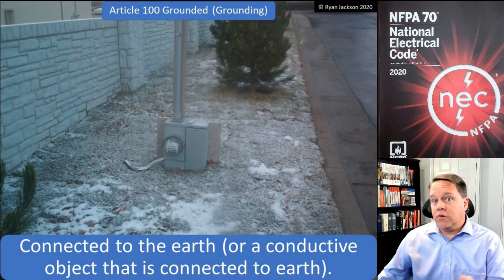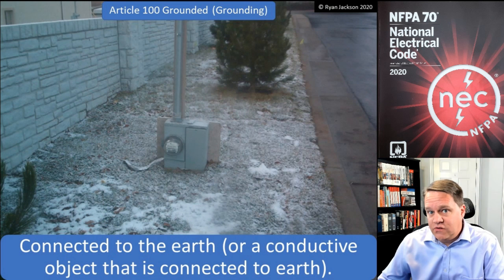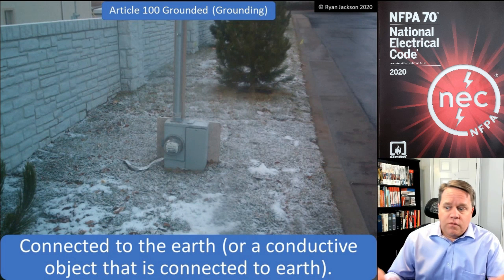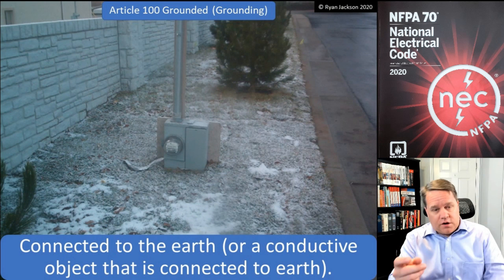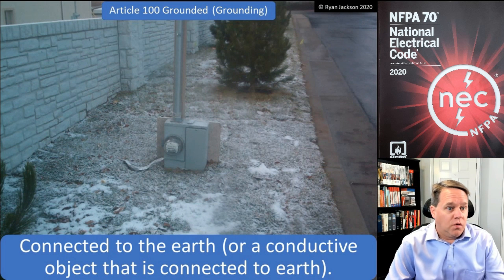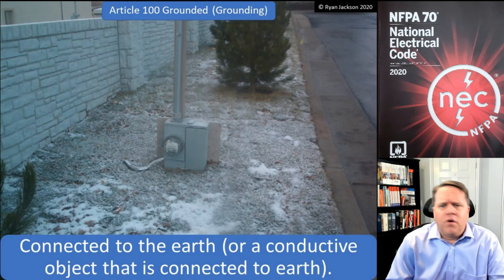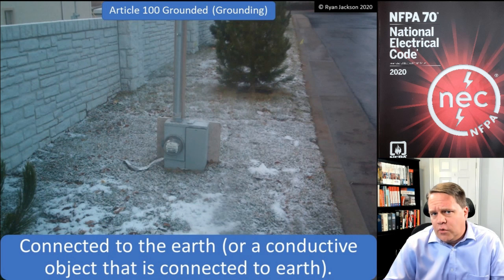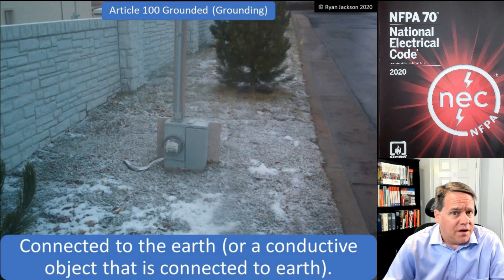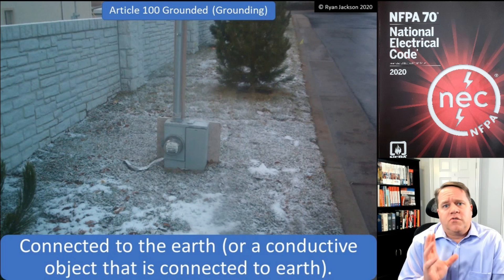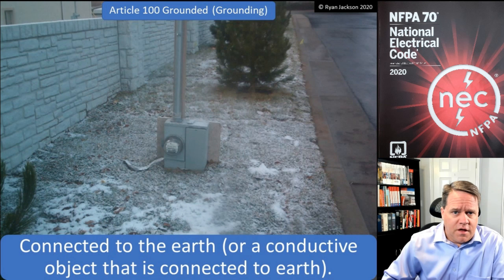So in the 2008 code, we stopped saying 'this shall be grounded' and instead started saying it shall be connected to an equipment grounding conductor, or connected to a grounding electrode conductor, or it shall be bonded. We started using more correct terminology. Because look — this is grounded. If you're told you have to ground your switches, as 404.9(B) used to say, does that mean you drive a ground rod at each switch, or put the switch in the dirt? Obviously they meant connect it to an equipment grounding conductor.